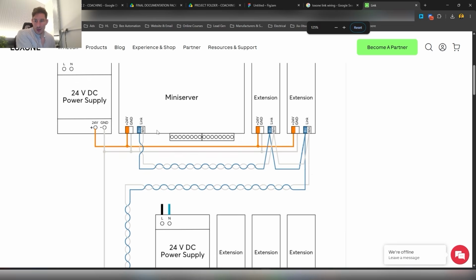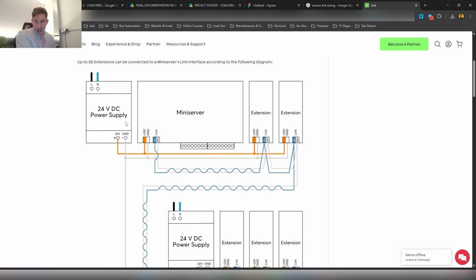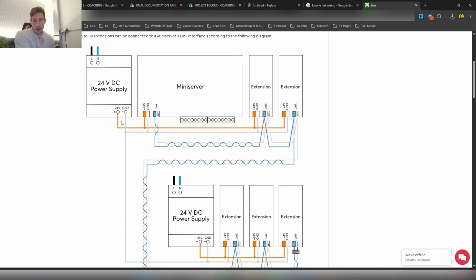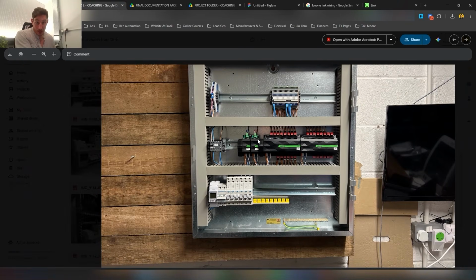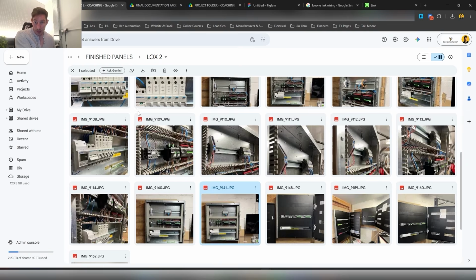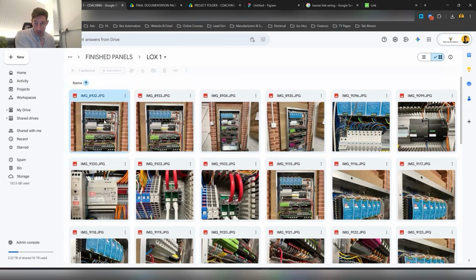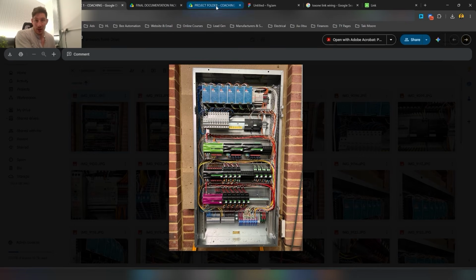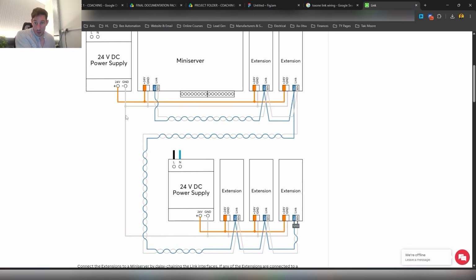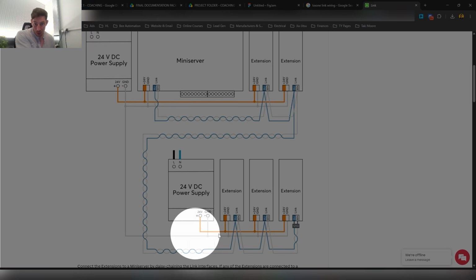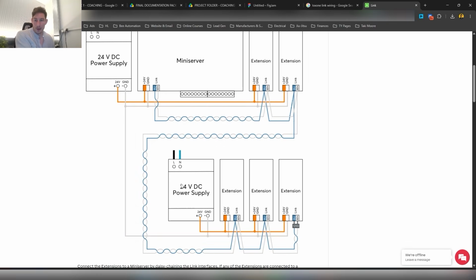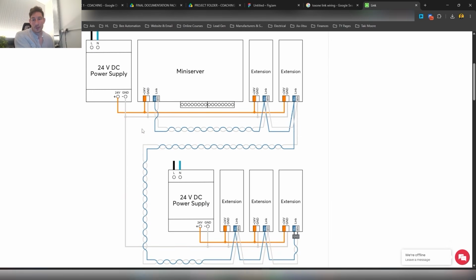Just going back to the power supplies, the reason they're in here is to show that if you've got power supplies across different panels - of which we don't in this panel, but in the other panel, Lox 1, we've got multiple power supplies - what this is showing us is we want to make sure we are commoning all of the 0 volts or ground across all power supplies, because all power supplies also feed each of these extensions as well, along with the link.